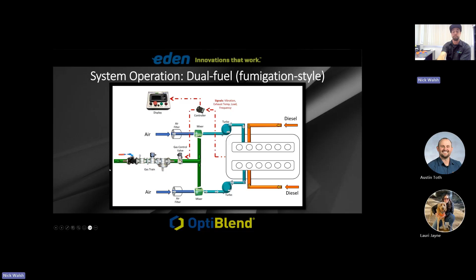No derating of the engine. In fact, we cannot tell an engine to do anything. We can't shut an engine down. We cannot derate an engine, nothing like that. Our alarms are set softer than the engine's alarms, so if anything starts to go wrong, our kit's going to shut off and your engine will be back on 100% diesel in an instant.